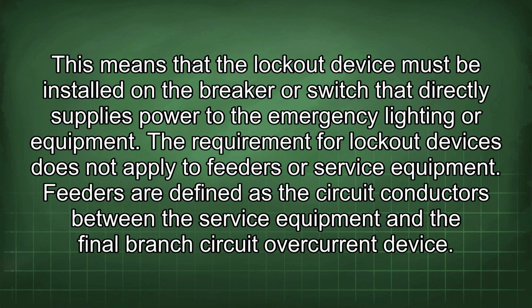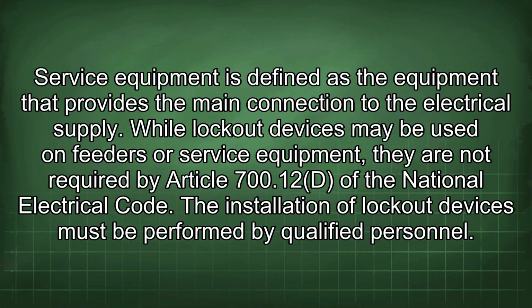The requirement for lockout devices does not apply to feeders or service equipment. Feeders are defined as the circuit conductors between the service equipment and the final branch circuit overcurrent device. Service equipment is defined as the equipment that provides the main connection to the electrical supply. While lockout devices may be used on feeders or service equipment, they are not required by Article 700.12(D) of the National Electrical Code. The installation of lockout devices must be performed by qualified personnel.